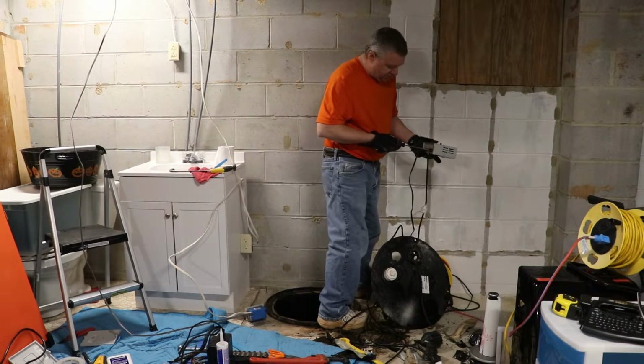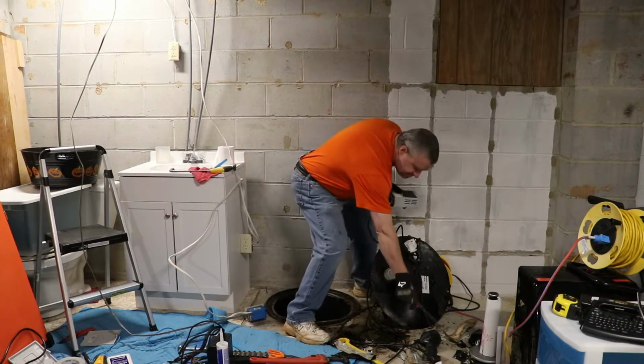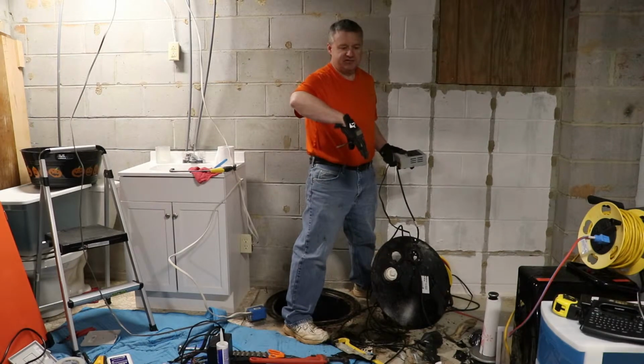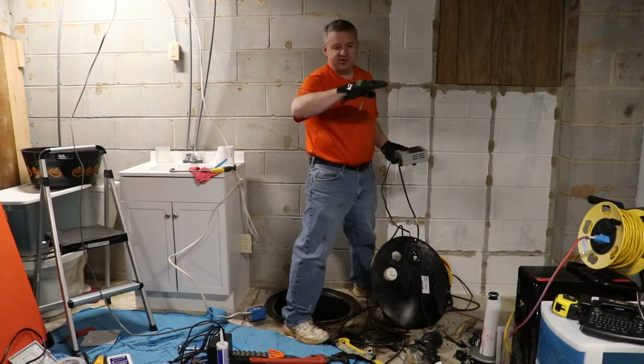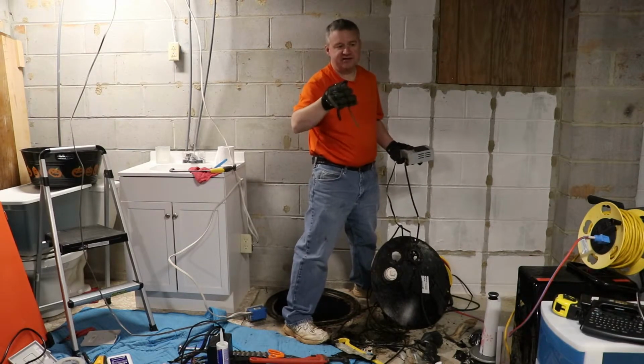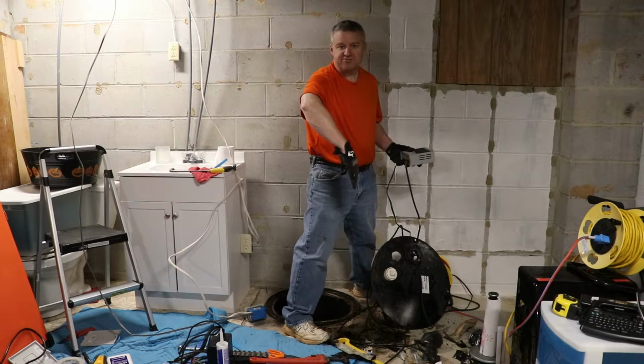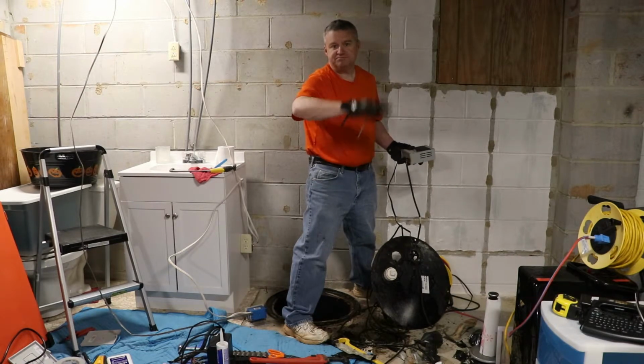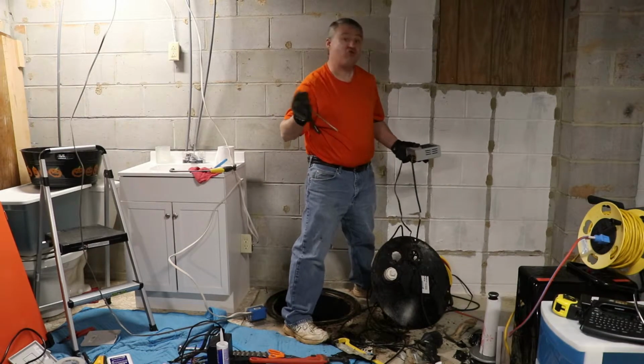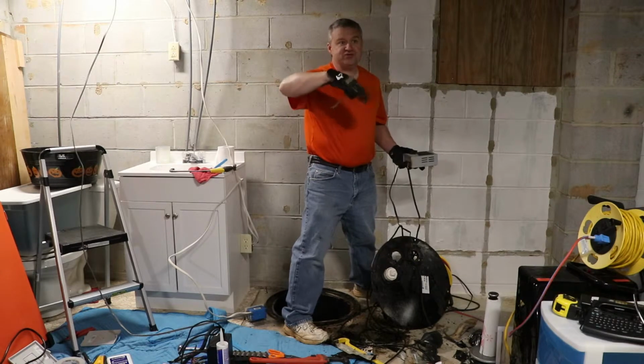These two wires are the alarm. This is what actually sets it off. Basically, there's two of these float valves inside the sump pump. The way they work is liquids come up and they start to float. When they float to a certain height, a contactor slides over, makes contact, and turns the pump on. So the way it normally works is, gets to a certain level, pump turns off, fluids get to a certain height, pump cuts on, back and forth. There's an additional float valve higher up, which is, for lack of a better word, your oh crap float, which means that, hey, your other one's not working and the fluids have gotten even higher than they're supposed to and the alarm kicks on.